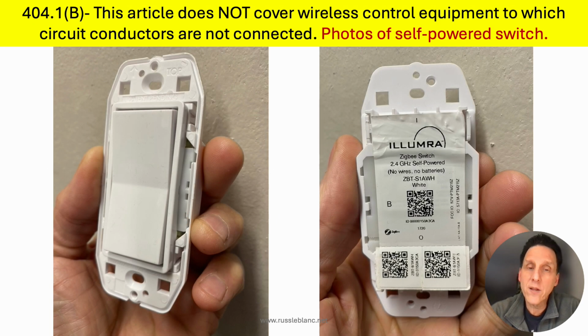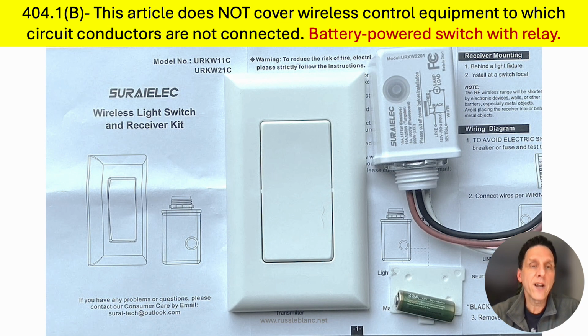All right, here are some wireless switches. This is a self-powered switch. There's no battery, there are no circuit wires. It's self-powered, and you tap it and it sends a signal to the receiver, and that can control the lights wirelessly. That's pretty cool. Here's another wireless switch. It's a battery-powered switch, and that sends an RF signal to a relay. So the wireless switch with no circuit conductors connected to it is not covered by 404.